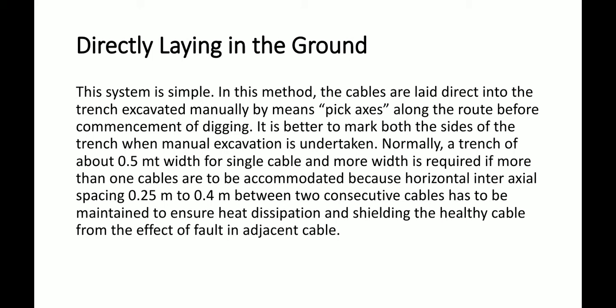Normally a trench of width 0.5 meters is used for a single cable. More width is required if more than one cable is to be accommodated, because a horizontal inter-axial spacing of 0.25 to 0.4 meters between two consecutive cables has to be maintained.